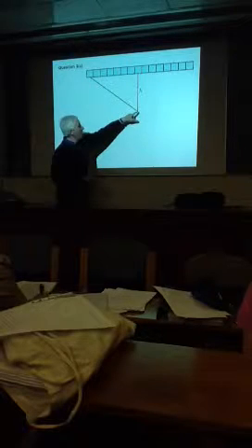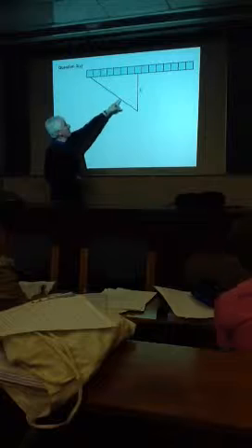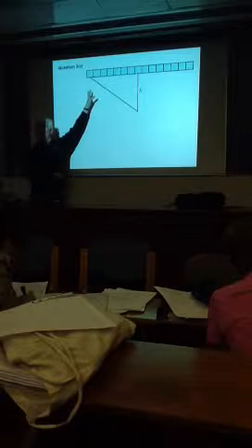Okay, so to answer this question, here I've drawn 15 elements in the group, and what the question is asking me is, for echoes which originate at a depth x below the center of the group, what is the delay that I need to add to the signal received at the element on the very end in order that it can be added or arrive at the same time as the signal from the central element in the probe.